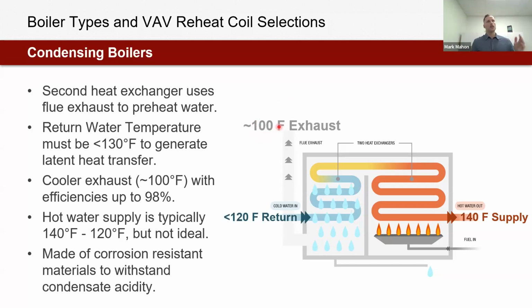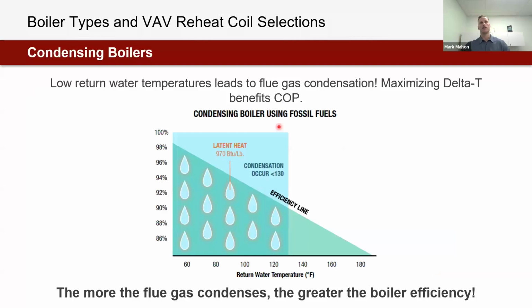The reality here is, the lower the return water temperature, the more latent heat transfer that we will have occurring within the condensing boiler. This boiler is made to be corrosion resistant. It can fully withstand the acidity of that condensation. And so we want a low return water temperature to have more flue gas condensation to benefit our COP. We can see here, we start to see condensation occurring at around 130 degrees Fahrenheit. The more it condenses, the more the boiler efficiency will grow.